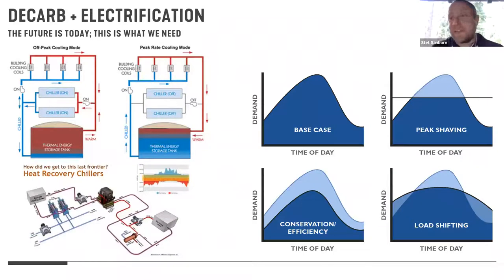So one of the things that we see, and a benefit that is almost a necessity here because of the grid layout that I showed you, is thermal energy storage or battery storage. It's really the same thing, just a different form. We use it because we are trying to do multiple things. We're trying to shave our peaks, because it saves our client money from demand charges. We're obviously trying to be really efficient, so getting that heat recovery heat pumps, we can get that enhanced COP if we're doing simultaneous heating and cooling. But the biggest thing that we're trying to do now is actually shift load.